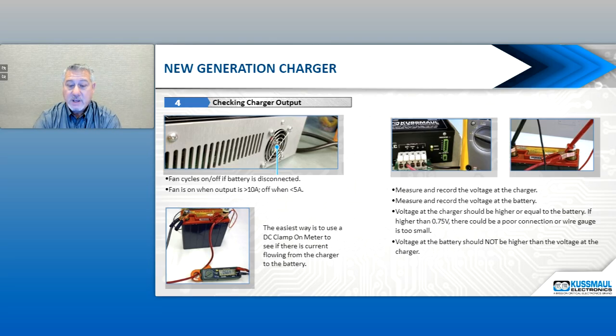Again, just like mentioned earlier, we want to measure and record the voltage at the charger, and also measure and record the voltage at the battery. The voltage at the battery and the charger should be closely the same, but it's possible the voltage coming out of the charger is slightly higher than at the battery. If the voltage at the charger is more than 0.75 volts higher, there's more than likely a problem within the wiring or a poor connection somewhere. The voltage should never be higher at the battery than at the charger.